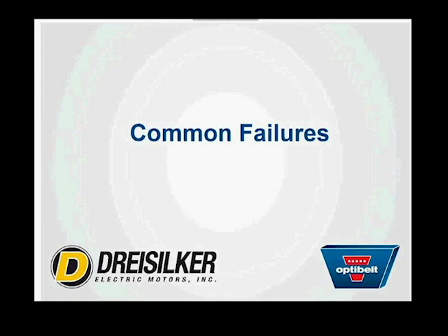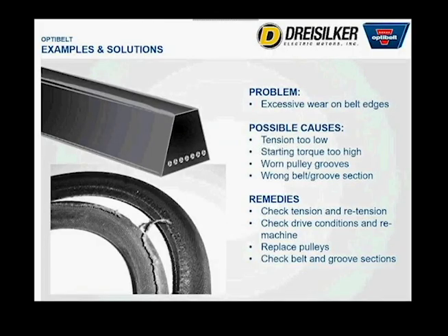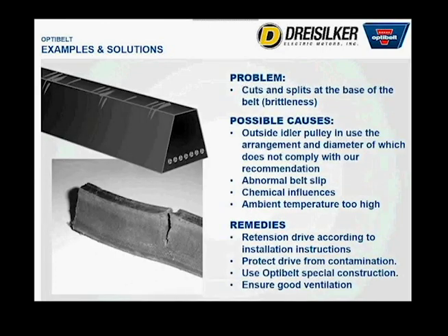So one of the common problems is excessive wear on belt edges, and this means that the belt is not riding properly in the pulley. It's either getting up on one side or in some cases turns over completely. So possible causes, again, tension too low, or your starting torque is too high, meaning that belt is jumping out and then the edges are running along the pulley and then it's finally settling back in. And then worn pulleys will also cause any sort of uneven wear on the side of the belt. So most of these are kind of bland. They just say check tension over and over again. But tension is a huge cause for failure.